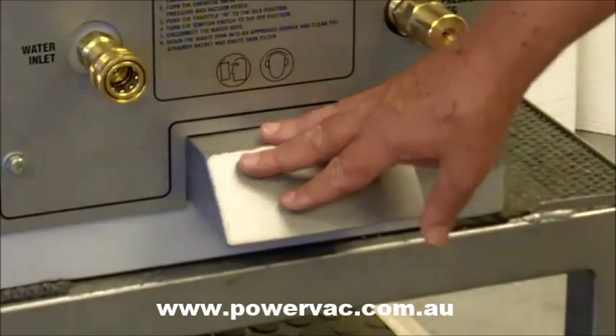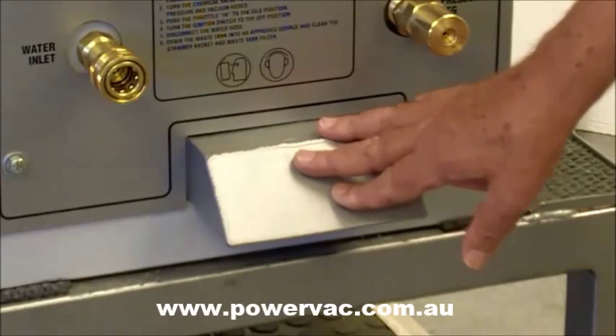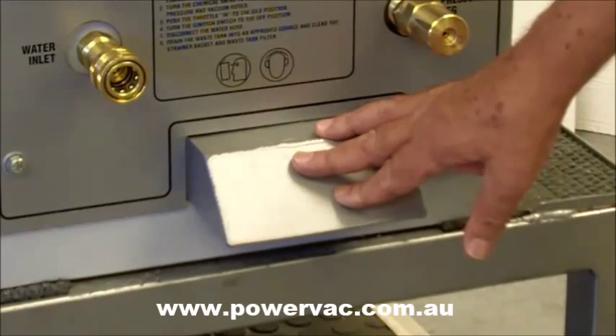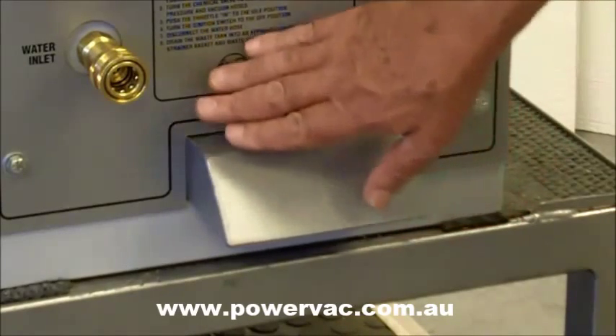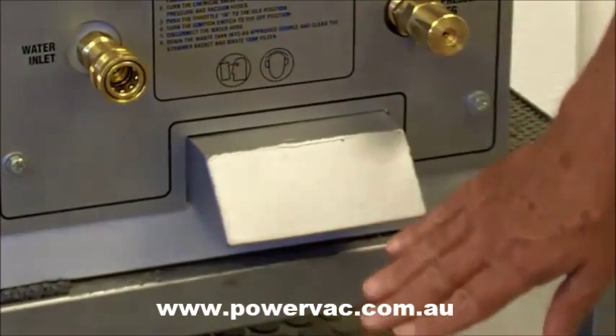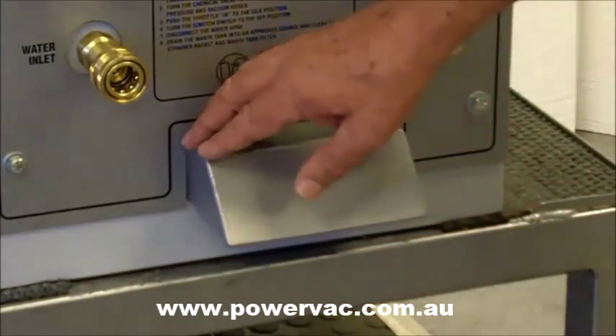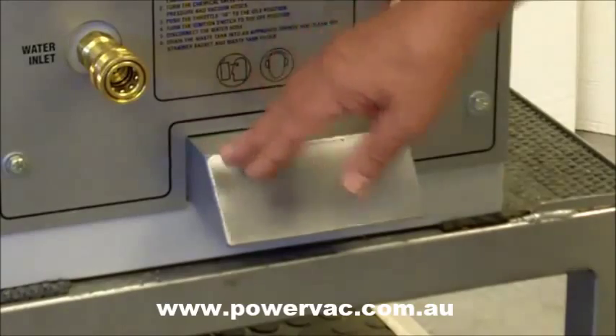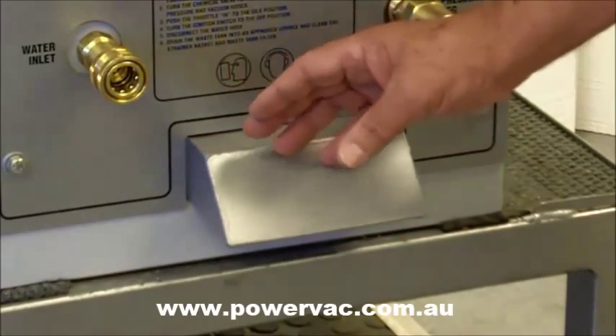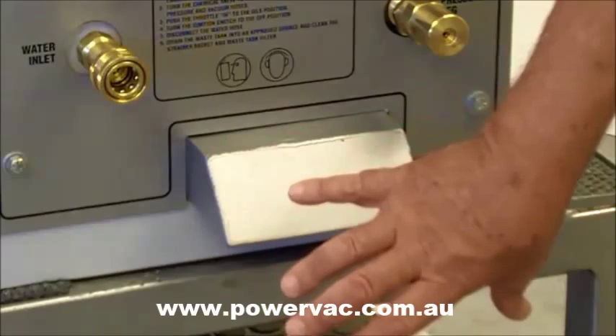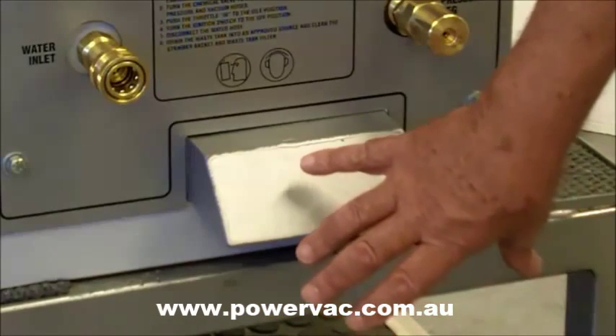In the center of the bottom of the machine is the exhaust outlet. This is both blower and engine exhaust. Right now it has the 45-degree turn down. If that doesn't work with the installation that you have in mind, this can be cut off, and we have a transition piece for a through-the-floor exhaust kit available.